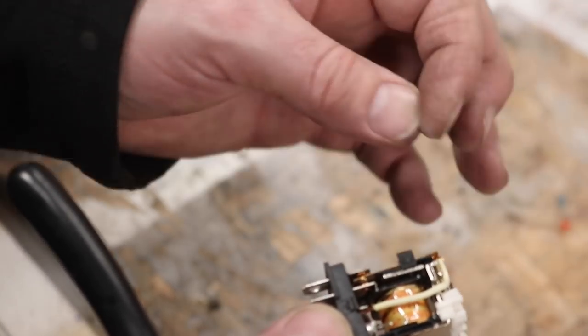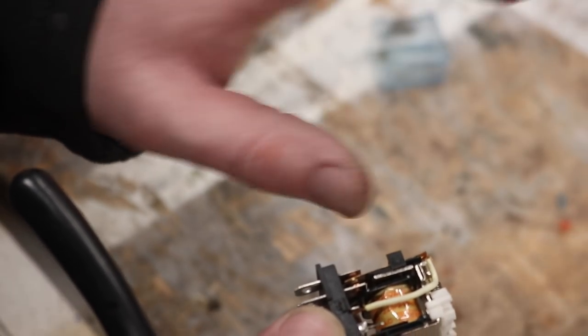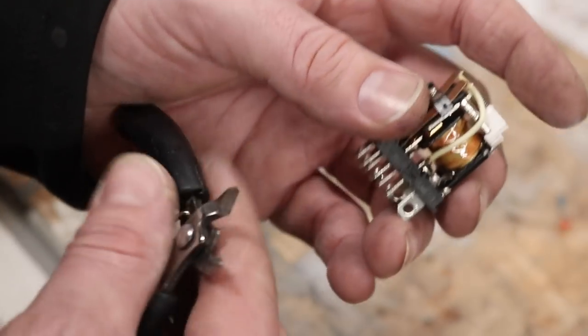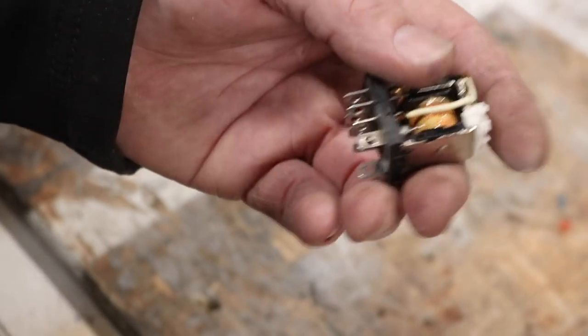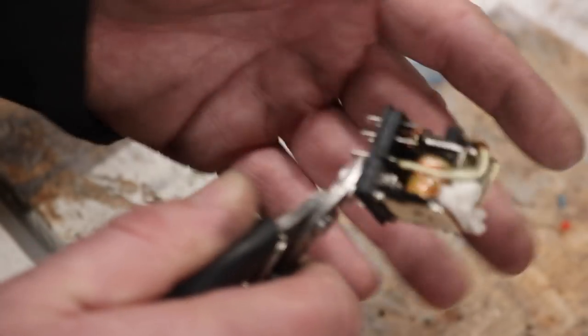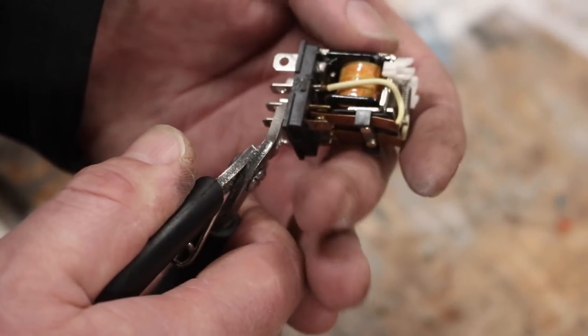For instance, the cooler that we've got this on at the moment actually has an over temperature thermistor. I think it's a thermistor, something like that, that when the temperature on the squirrel cage motor gets too high, it breaks the circuit. It's like over temperature protection for the whole thing, and the same in the compressor as well for the chiller. So if it fails open circuit, or closed circuit, sorry, then there's other parts of the circuitry which will take care of it.